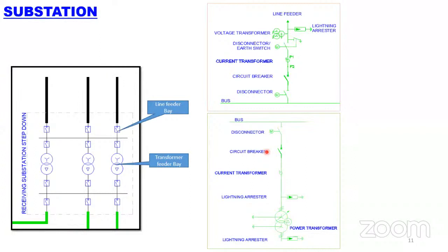Okay, what are the components in the power transformer? It is similar to a line feeder: number one, the disconnector, the circuit breaker, then the current transformer, which helps to monitor the current flowing into the power transformer. Then finally the lightning arrestor. Lightning arrestor, because the power transformer is a prime piece of equipment, and the major cost of the substation is because of the power transformers. So we need to give real protection, especially for the power transformer. What we need to place mandatorily is the lightning arrestor on the primary as well as the secondary of the equipment. That is mandatory.